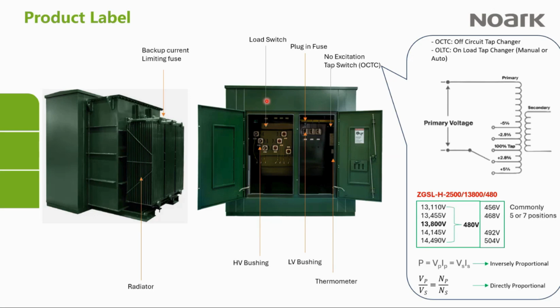Then we have the load break switch, which I'll talk about later on. But basically, why we say it's a load break switch is because you can use it while the transformer is on load, while the transformer is actually supplying power to a load. So that's why we call it a load break switch. Then you also have here the tap switch. In this case, it's an off-circuit tap switch.